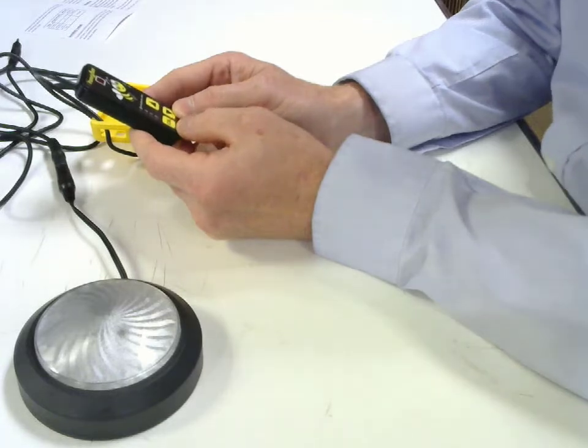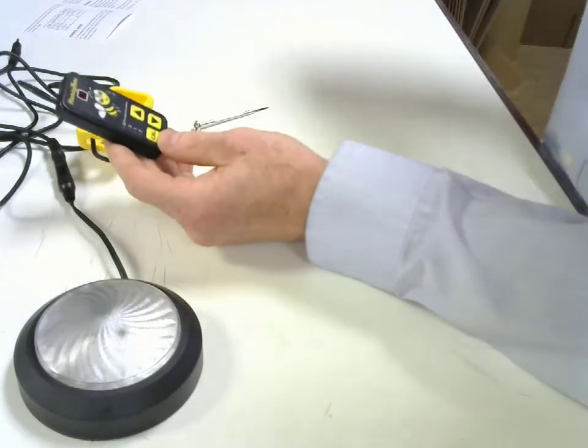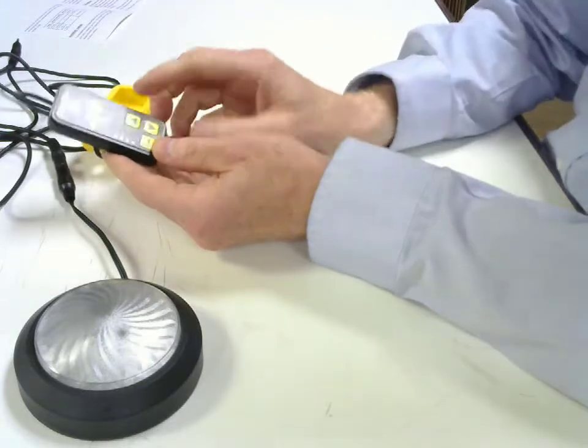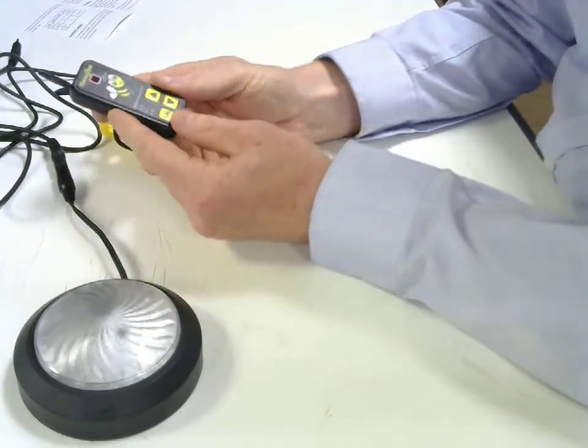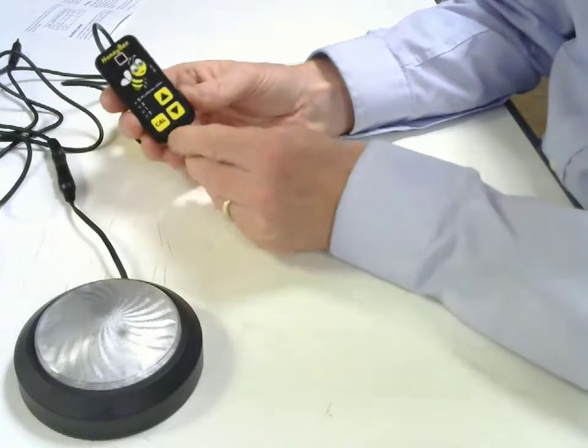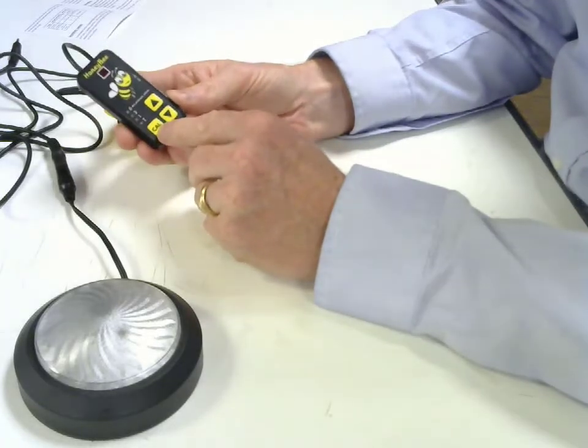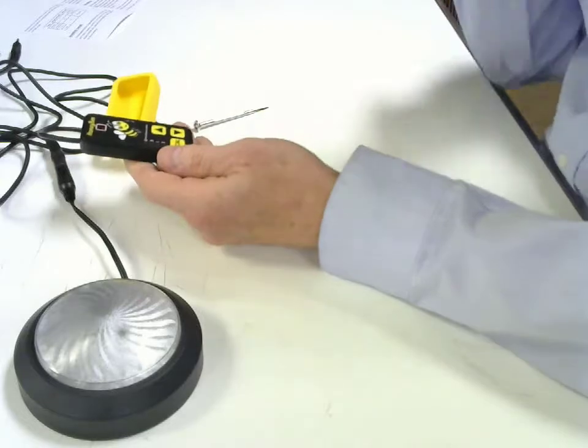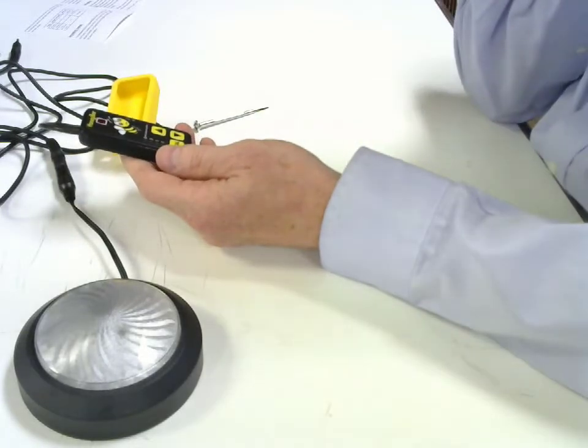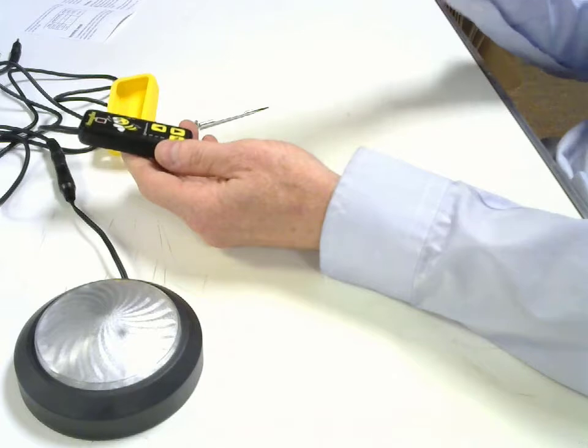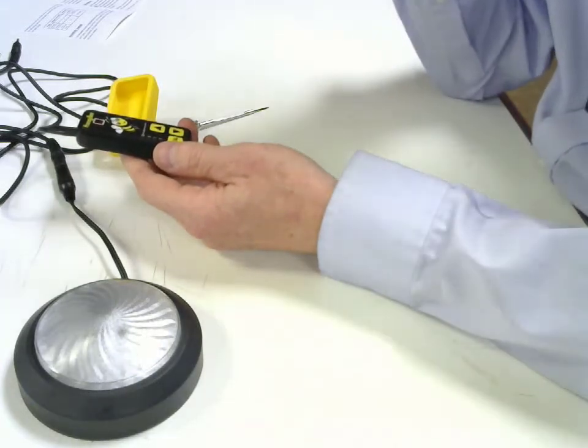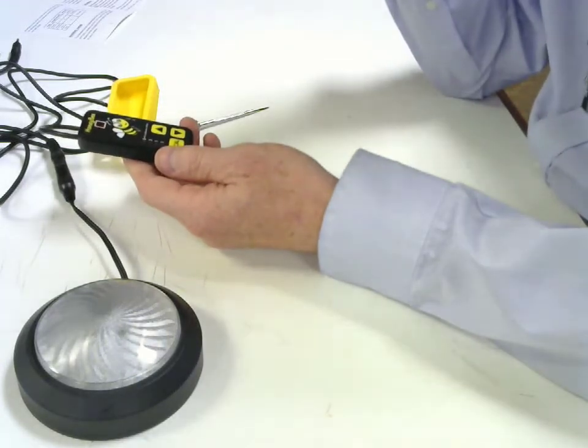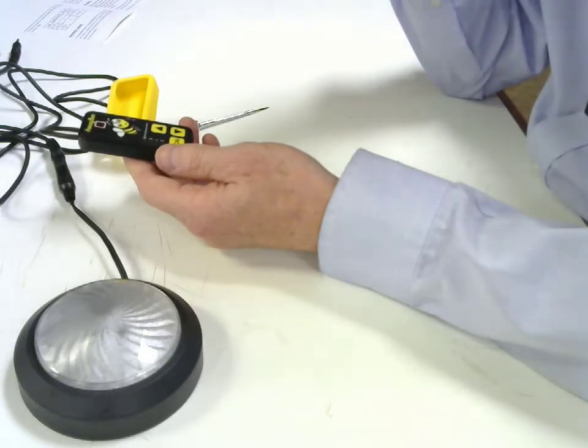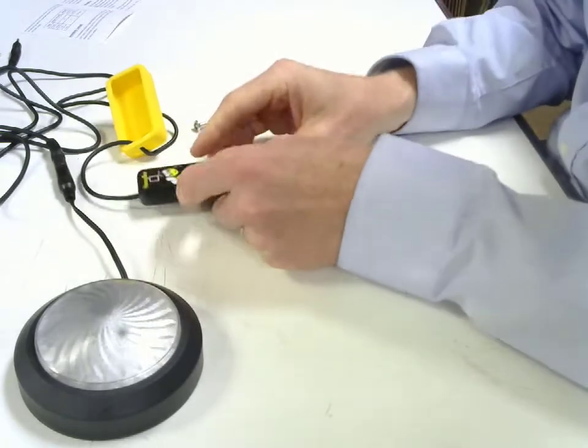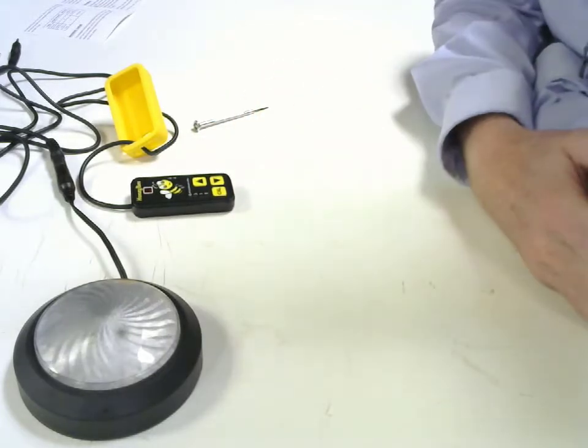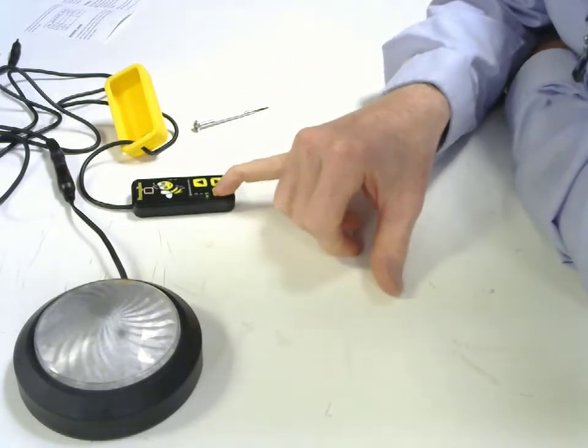So let's see, what shall we explain? I think I want to talk about calibration. Can't really read it here, but there's a feature on here called calibration, and it's called CAL. And what that is: every now and then the HoneyBee will drift. It can drift over time because of temperature. The effect of the drift is you'll end up with a HoneyBee that's either more or less sensitive than the desired range. And when that happens, all you really have to do is recalibrate.